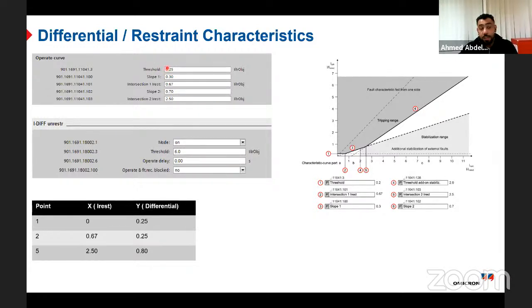On the high voltage side, you define the threshold, which is the minimum operating current, slope 1, then the intersection between slope 1 and slope 2, then slope 2, then you define the intersection of slope 2. So you need an intersection point here, number 2, which is defined here as intersection 1, I restraint, and number 5, which is the intersection of intersection 2. Based on this, you can draw the characteristic. You can do the calculation, use trigonometry and find the intersection between slope 1 and slope 2, then draw the characteristic, and at the end, you will do some homework to understand.